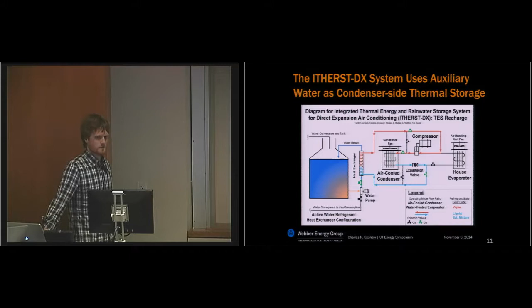In thermal storage discharge mode, the compressed vapor bypasses the air-cooled condenser and goes through a heat exchanger that's being cooled by water from the tank. The condensed refrigerant then goes through the same expansion valve into the same evaporator for the house. This is at a much lower temperature than the outdoor air, and I'll explain why that's significant on the next slide. For recharge mode, instead of going to the house evaporator, it goes into this heat exchanger again and cools the water down, just like you'd be cooling the air down inside your house.